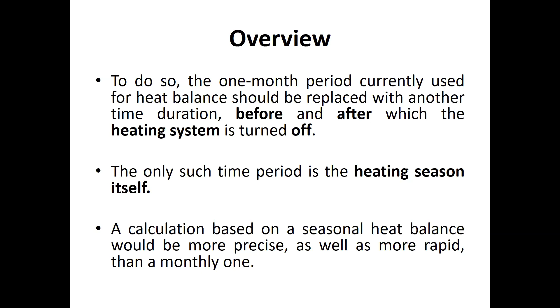And what is the time period where the heating system is turned off before and after it? There's only one, and that's the heating season itself, the whole heating season. So a calculation based on a seasonal heat balance would be more precise because these two causes of uncertainty, of inaccuracy, Q residual and Q shifted, are absent. And besides, this will be much more rapid because we will have one balance for season instead of 6 balances.